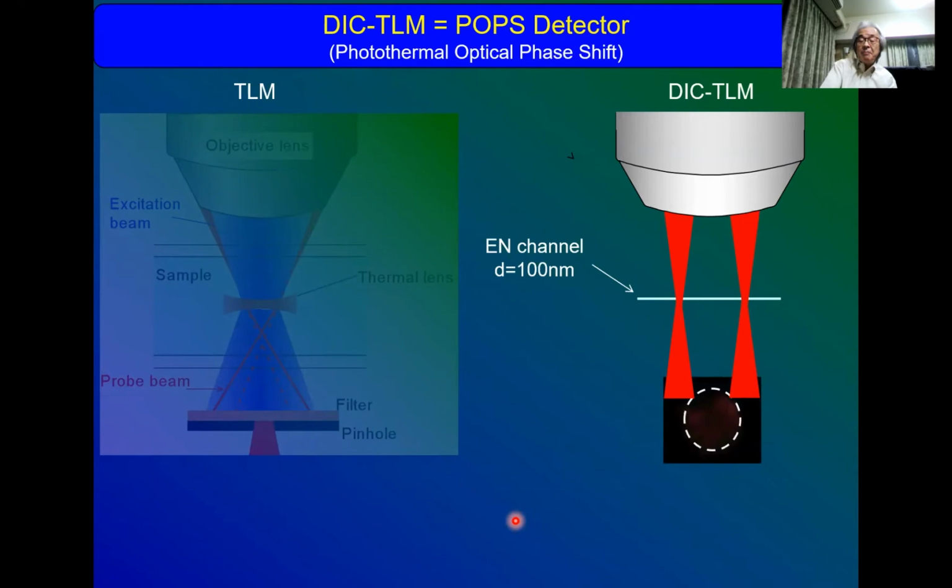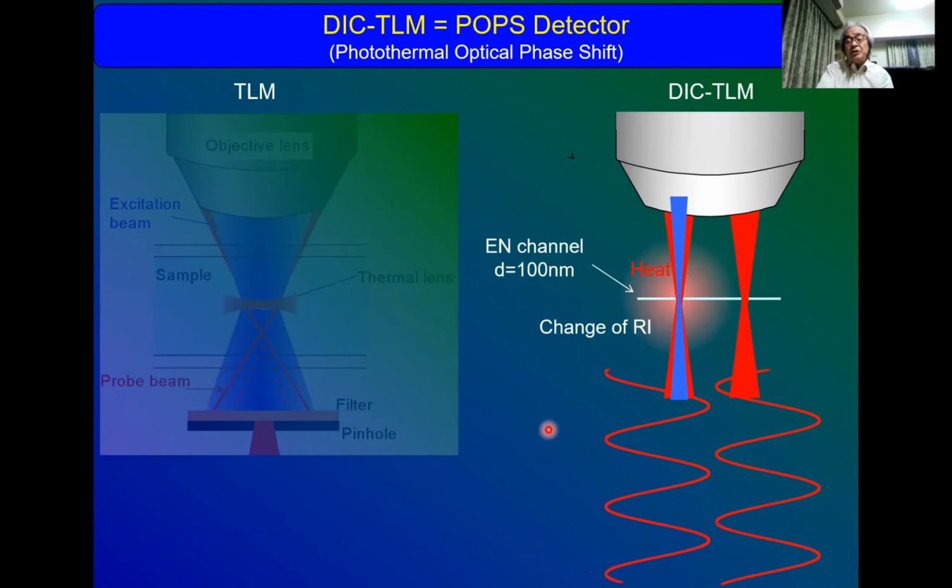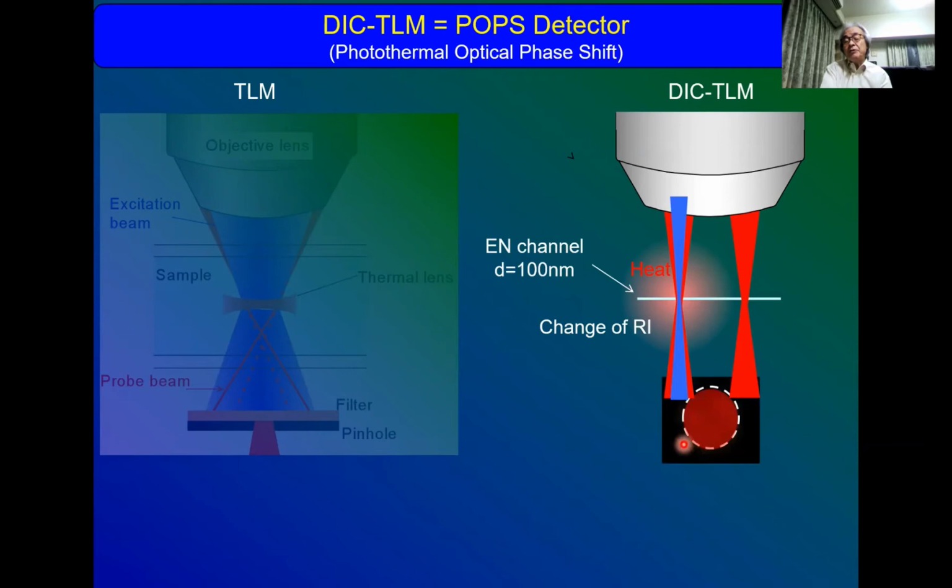However, if we introduce an excitation beam and there is a target molecule, the target molecule emits heat, and the heat changes the refractive index, and then a phase shift occurs from the refractive index change. After the phase shift, the interference still leaves some part of the light. From the intensity of this interference light, we can know how many molecules are there.